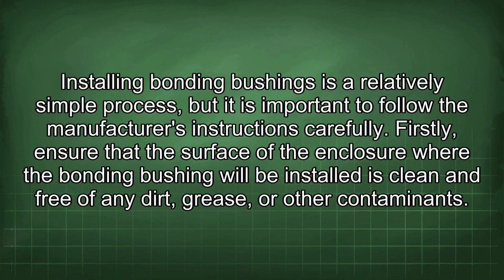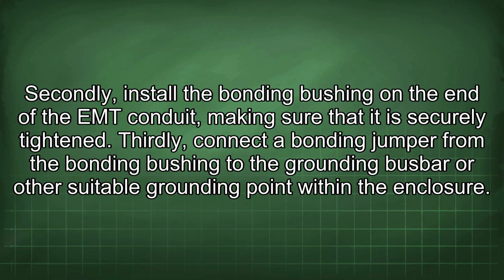Installing bonding bushings is a relatively simple process, but it is important to follow the manufacturer's instructions carefully. Firstly, ensure that the surface of the enclosure where the bonding bushing will be installed is clean and free of any dirt, grease, or other contaminants. Secondly, install the bonding bushing on the end of the EMT conduit, making sure that it is securely tightened.